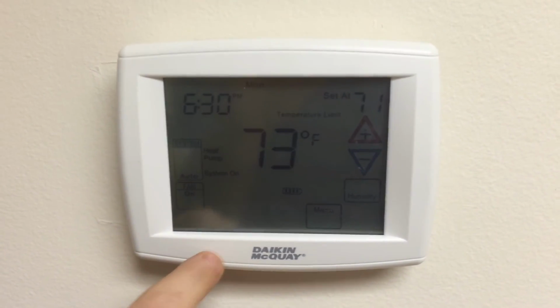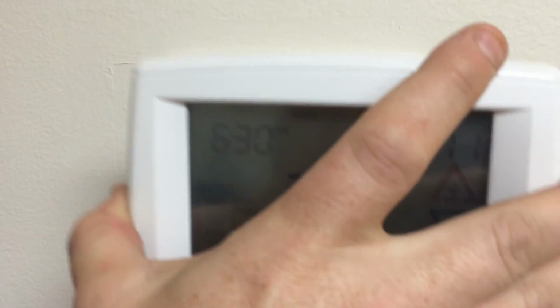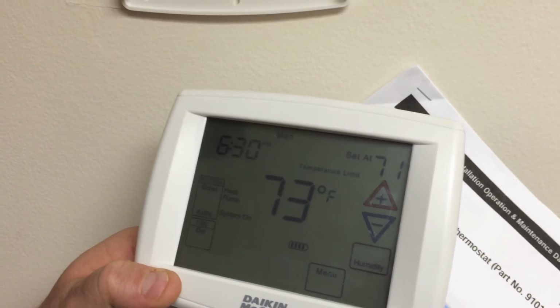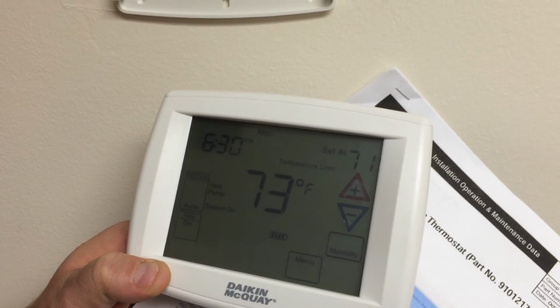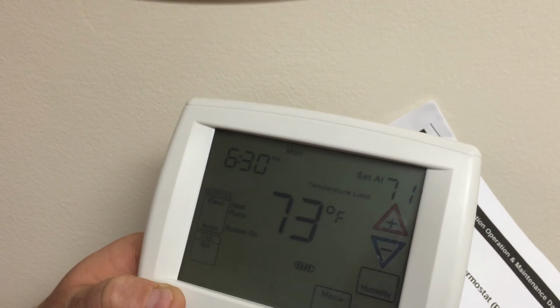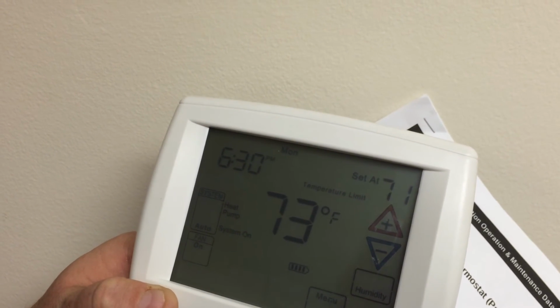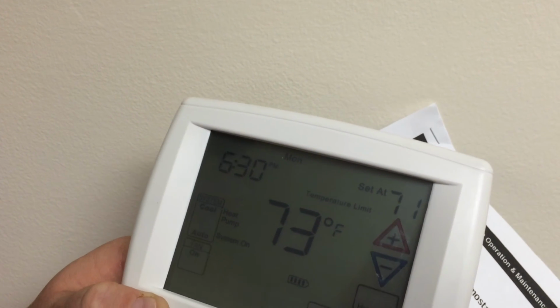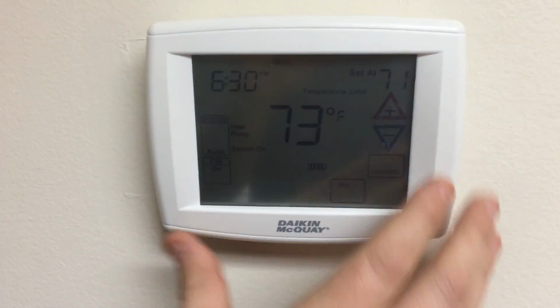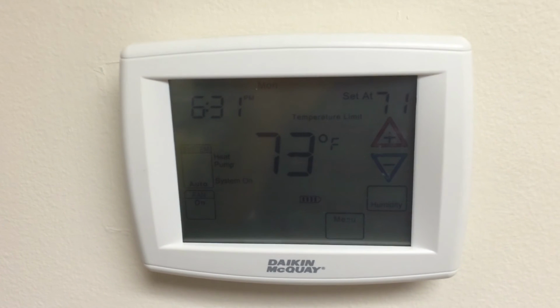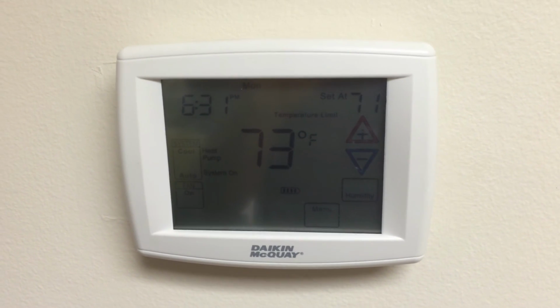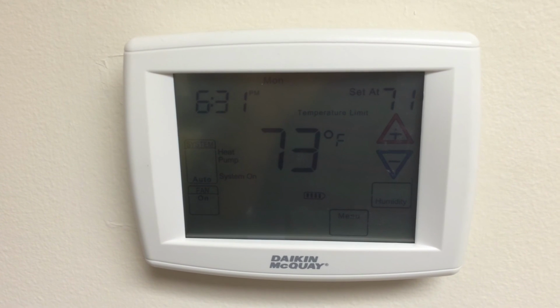The nice thing about these units, though, is that if you take it off the wall, you notice that the unit is still on, and you can go sit down at a chair somewhere and program your schedule in this thing. I have a few maintenance guys that will just grab them all off the wall, change all the batteries, and sit at his desk and program them all while he's at his desk. Take them back out to the rooms, plug them in, hit run schedule, and we're good to go. That is the end of the Daikin McQuay programmable touchscreen thermostat.